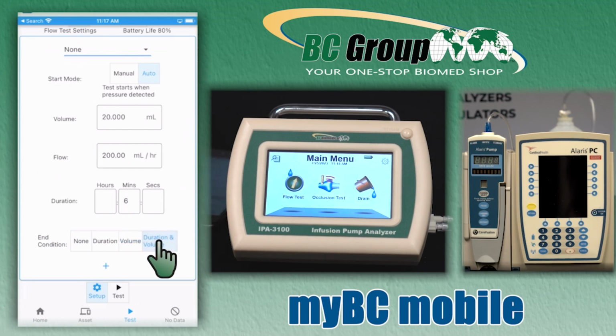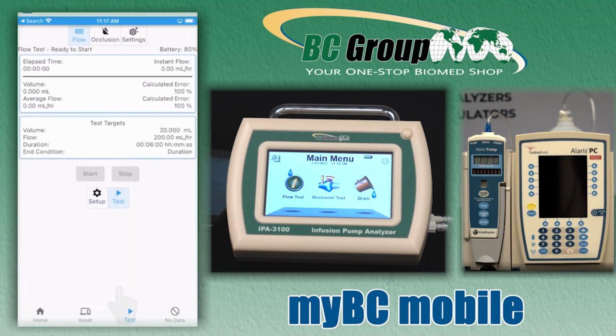Or we can do both duration and volume, where I have to hit 6 minutes and I have to deliver 20 milliliters. Both conditions have to occur. So it would have to be greater than 6 minutes and at least 20 milliliters for the test to stop. So I'm just going to pick duration. We'll run a 6-minute test and see how the results go from there.